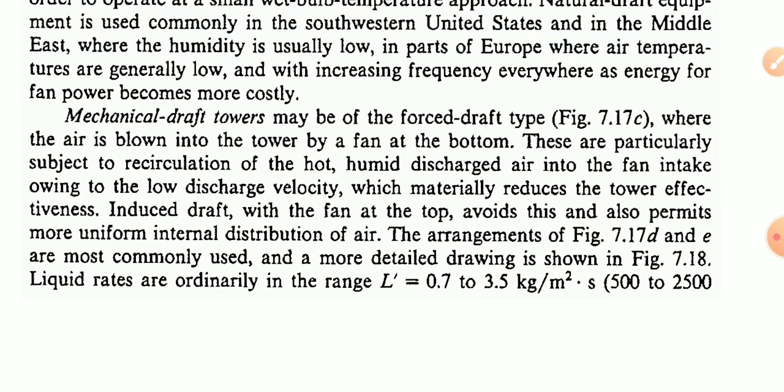Now the mechanically draft tower may be of the forced draft type, where the air is blown into the tower by the fan at the bottom. These are particularly subject to recirculation of the hot and humid discharge air into the fan intake owing to the low discharge velocity, which materially reduces the tower effectiveness.